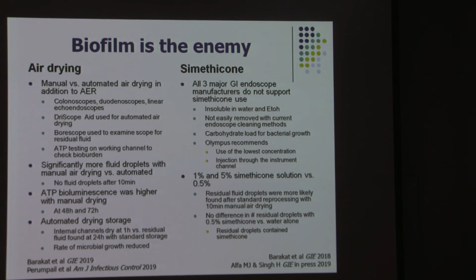The carbohydrate load in it could be a source for bacterial growth, and the manufacturer recommends use of the lowest concentration and injection through the instrument channel rather than putting it into the water pump. There was a study comparing use of lower concentrations of simethicone and found that with the lowest concentration, you have the lowest chance of having droplets.